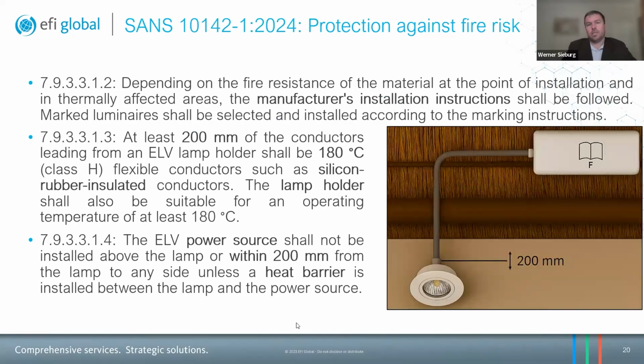So then, carrying on with protection against fire risk, depending on the fire resistance of the material at the point of installation and in the thermally affected areas, right? This is above and below the lamp. The manufacturer's installation instructions shall be followed. That's also very important, because manufacturers also very often dictate or say, this is the amount of heat that you can expect to be generated by this lamp.